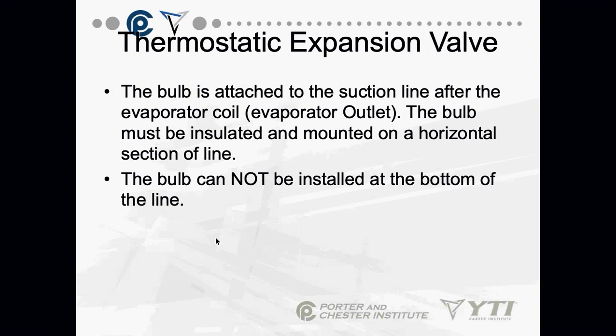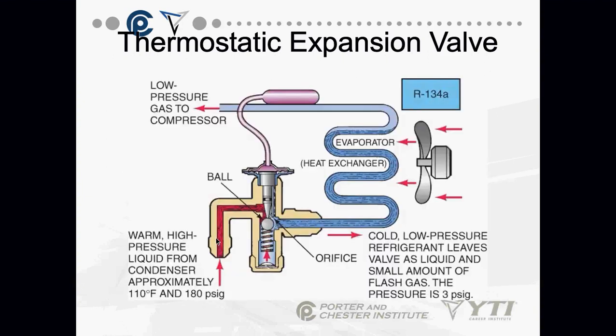line. The bulb cannot be installed on the bottom of the line. I'll show you a diagram here in a minute. Because the bottom of the suction line has some oil in it.